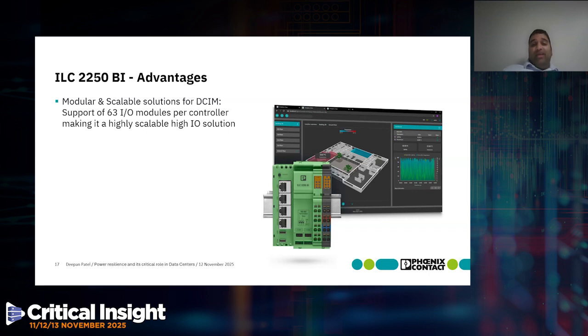What does that mean for a data center project? Importantly, it means you can be very scalable. No matter how small or big the I/O requirements are, and a lot of these data centers need to monitor breaker statuses, ATS, and temperatures with the chilled water systems the data center uses, that type of scalability is important.